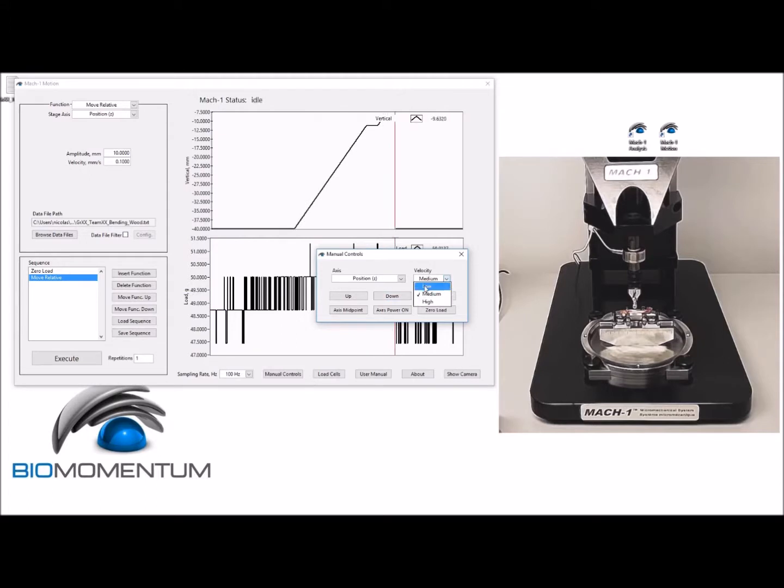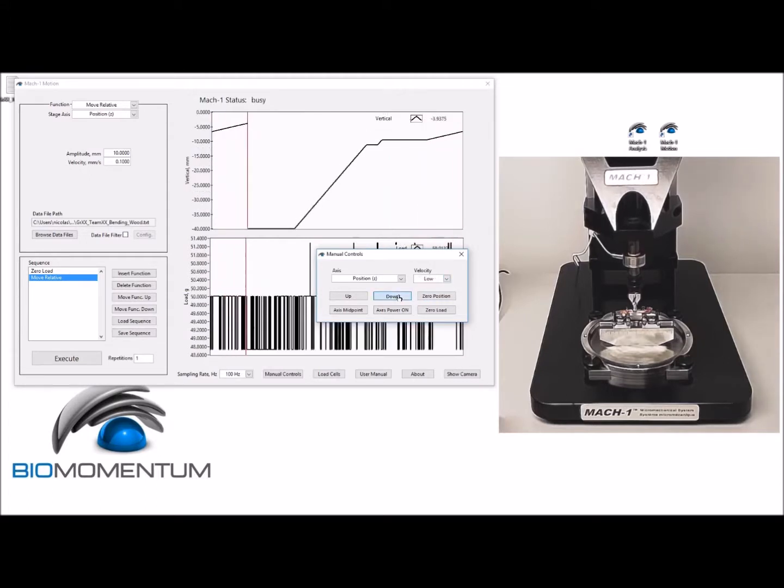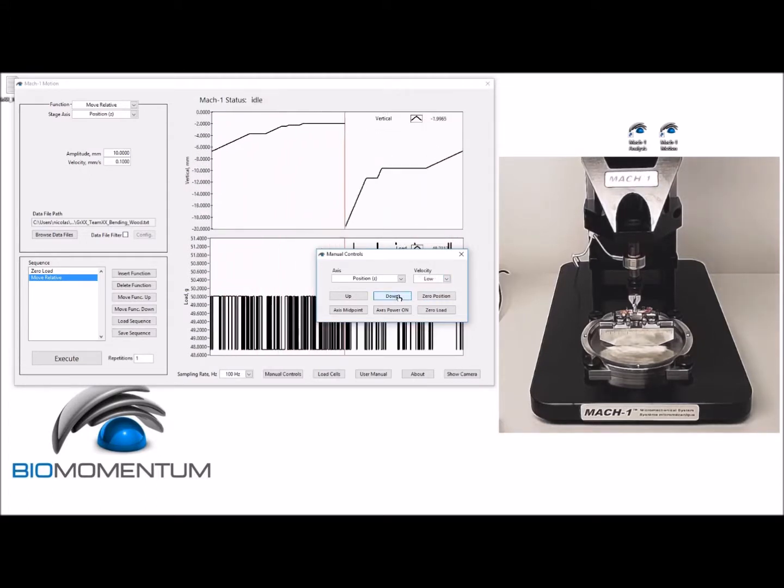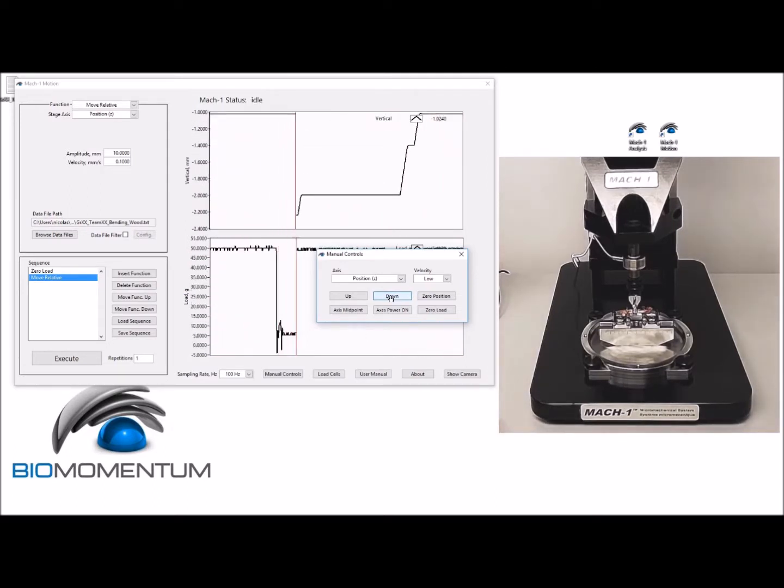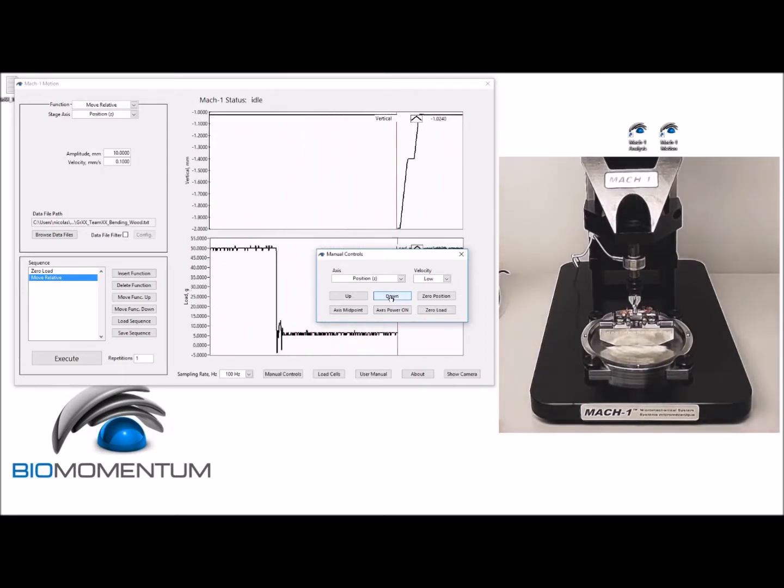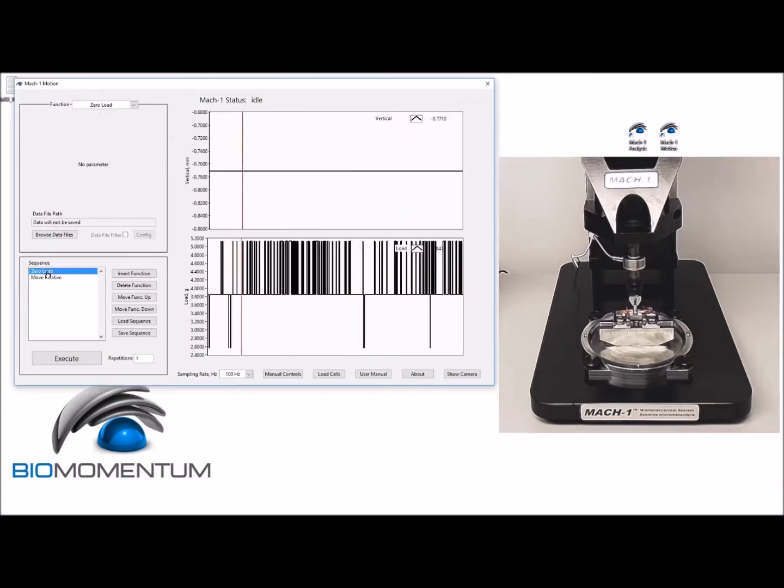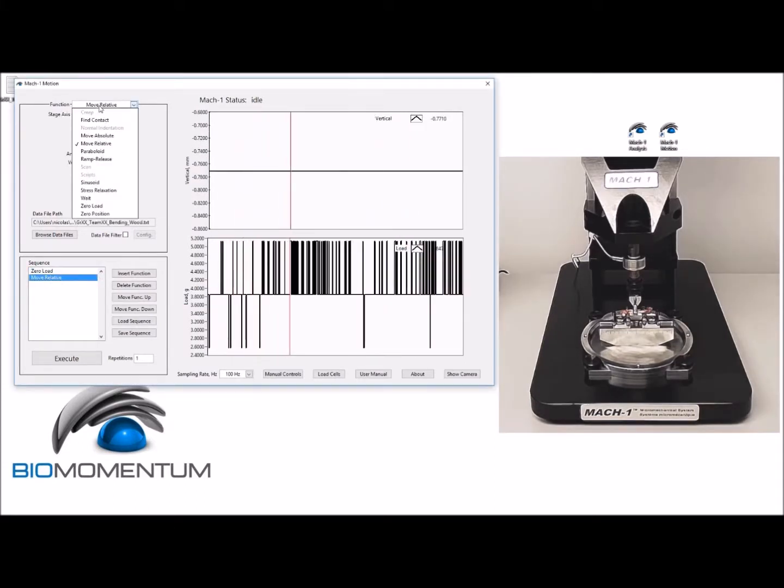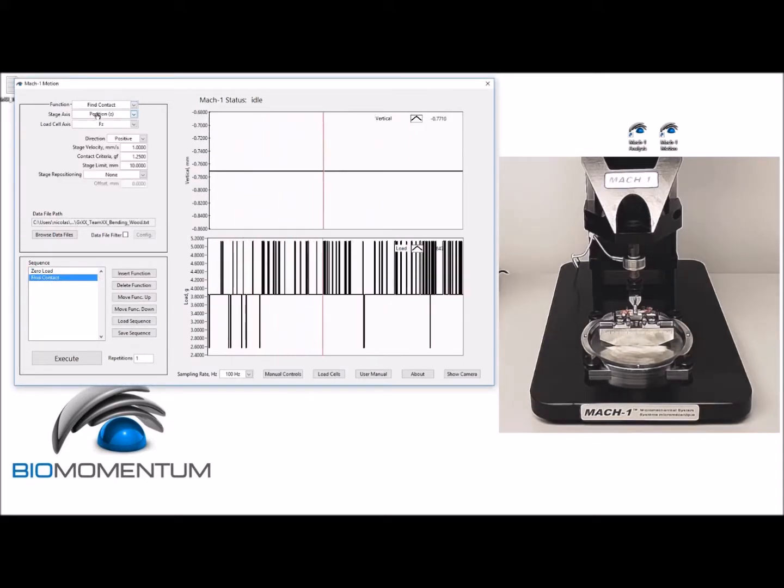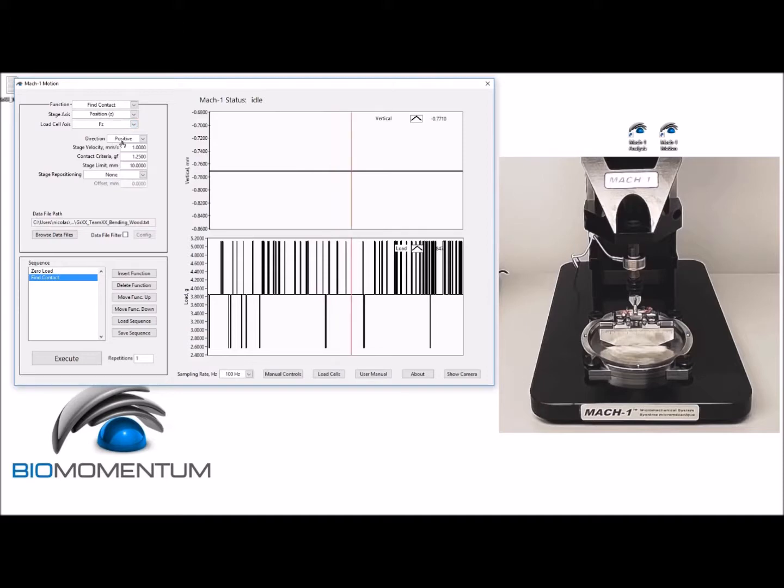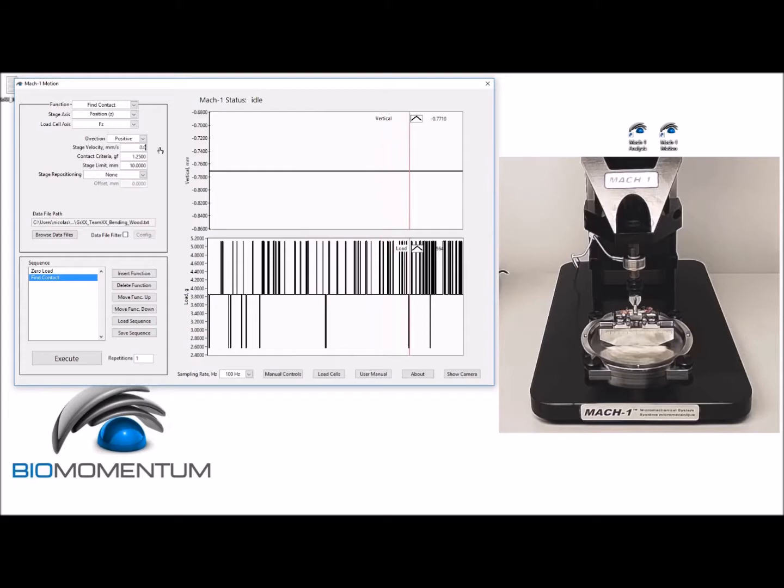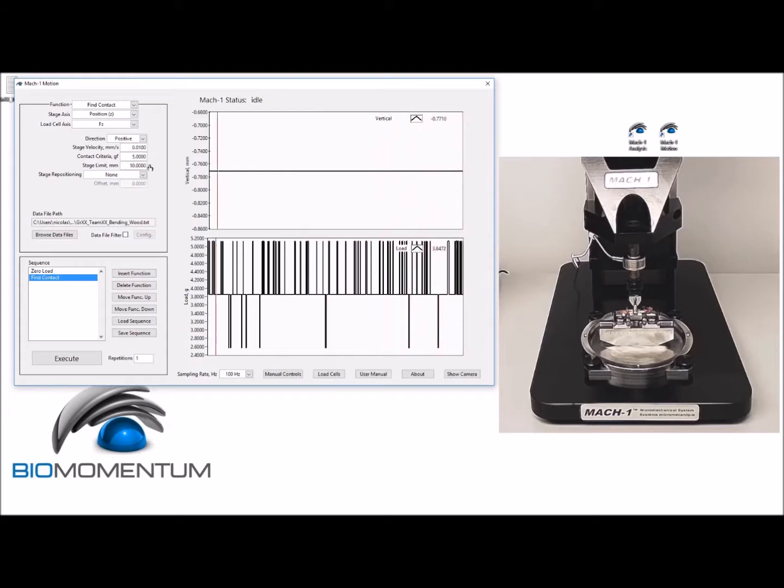above the sample, and at low speed to approximately 2 millimeters above the sample. Then perform the following test sequence to find the surface of the sample: a zero load followed by a Find Contact function with position Z as the stage axis, the force in the Z direction as the load cell axis.